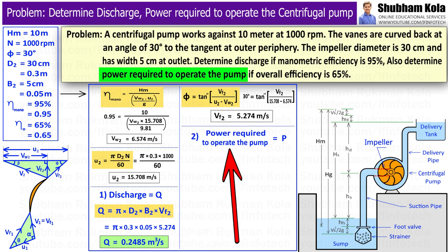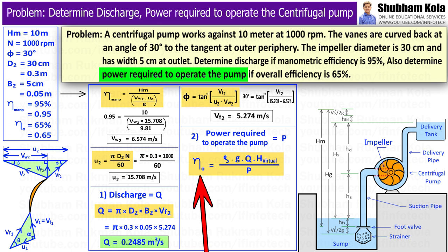We want to calculate power required to drive the centrifugal pump. To calculate power required to drive the pump, i.e. shaft power, I will use the overall efficiency equation which is equal to power output, rho gQ into virtual head Hv2, whole term divided by shaft power, where virtual head represents the total head through which liquid can be lifted when all friction losses in pipes, impeller and casing are neglected.